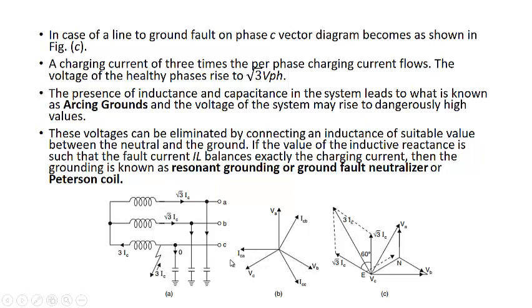But if a single line to ground fault occurs first, and then after this another line is involved in the fault, there will be a line-to-line fault and a triple line fault. So here the disadvantage is that the phase values will increase to the line voltages, and protection is not guaranteed. This single line to ground fault is not detected.